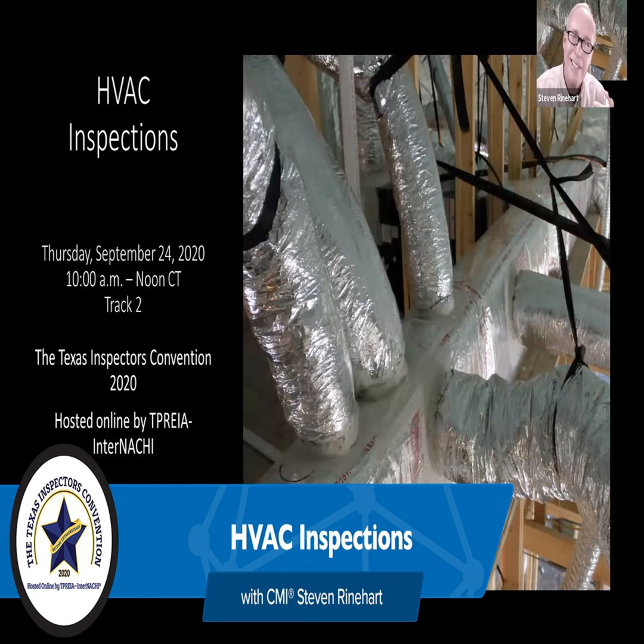That's a problem. I like them outside the house if they're gas, outside the living space. If it's inside, I'd like to compartmentalize it and seal it. And that includes the ceiling. It does not need to be freely communicating other than the combustion ducts that are just the minimum required there. You don't need to take the whole ceiling out. And a lot of times that thing is wedged in so tight, it's sweat, it's leaked, it's gotten the ceiling so wet that it's falling apart and nobody's gone in to replace it. I'll put that in my report, the ceiling's missing.